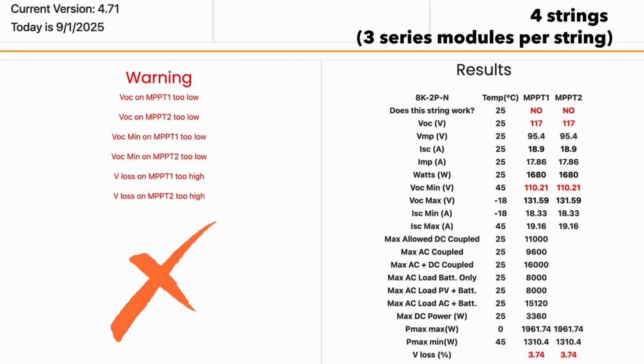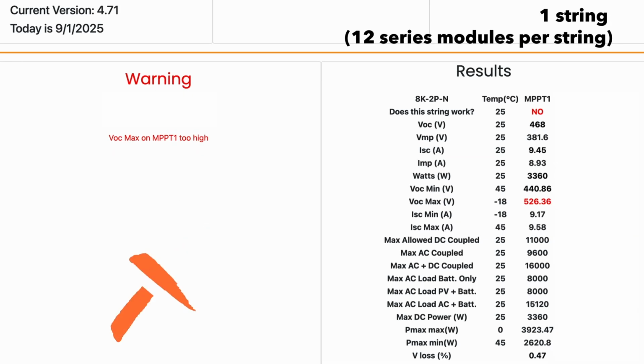So I did some calculations to figure out the best string voltage to match the Sol-Ark inverter. I first looked at whether I could put all 12 solar panels in series and have one string going to the inverter. Unfortunately, the maximum VOC was higher than what the Sol-Ark could handle, just barely. About 11 panels in series would have worked fine.